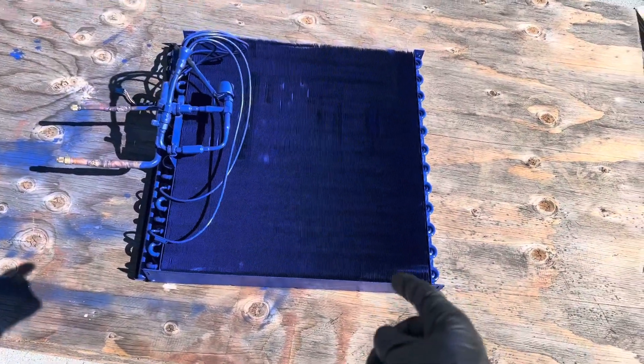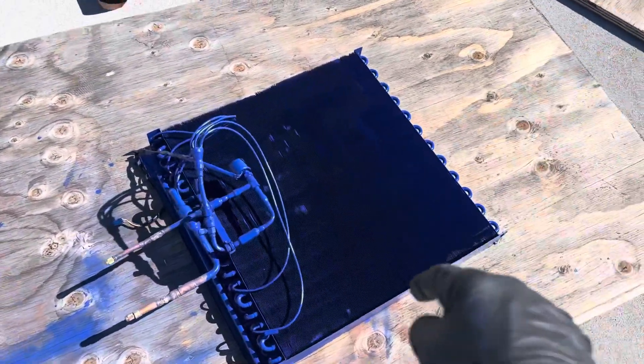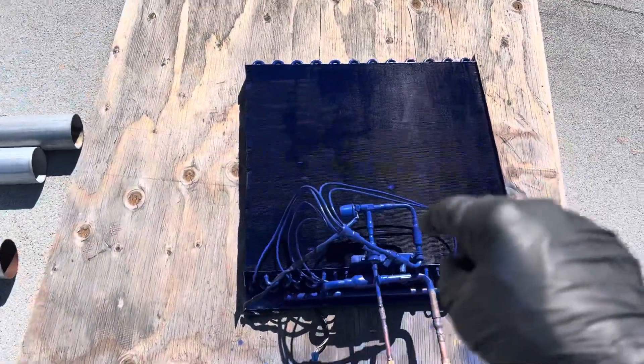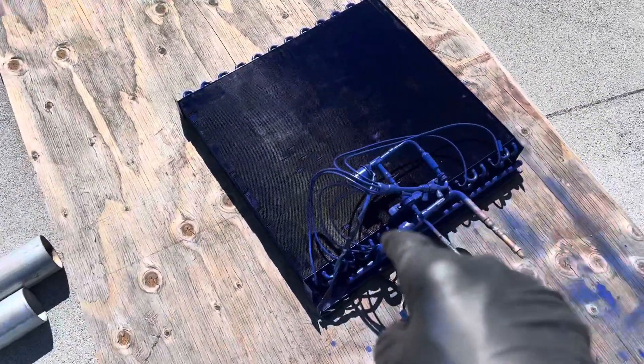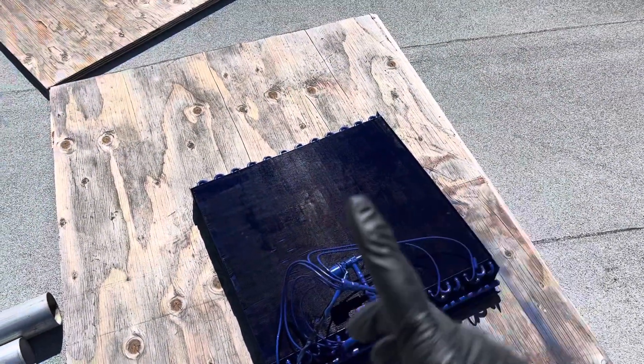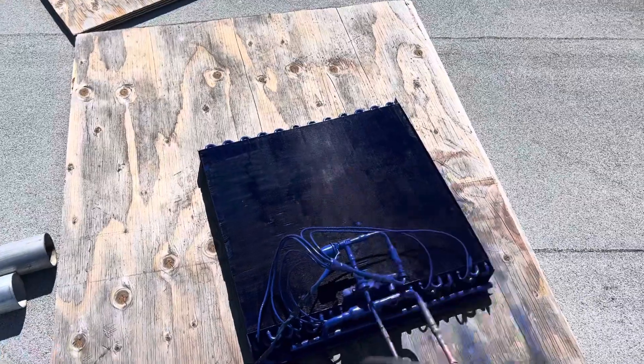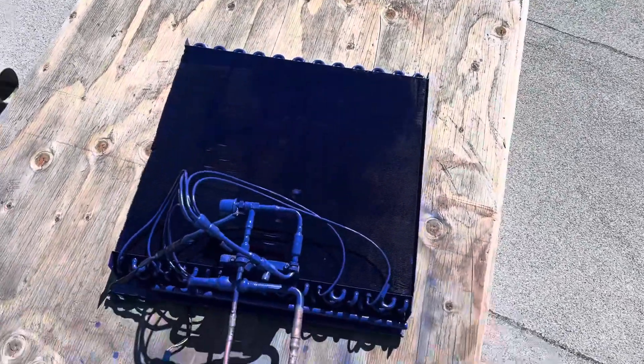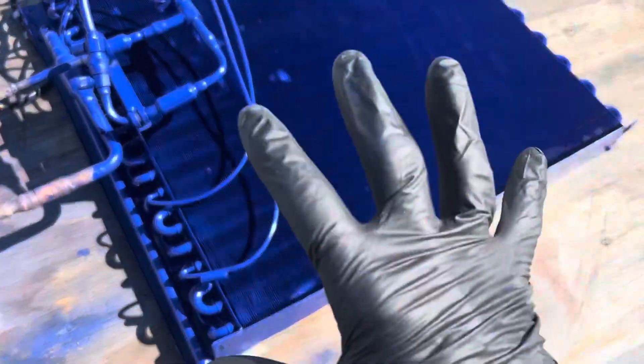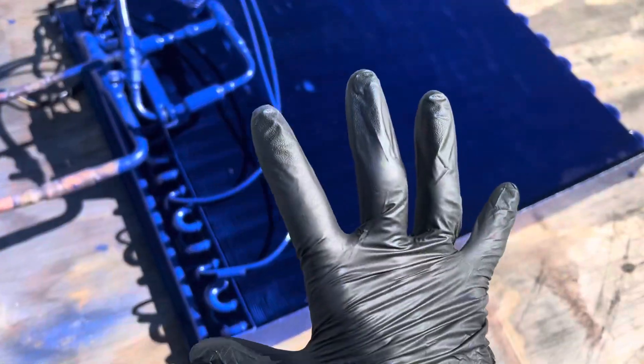This is the evaporator from a five-ton commercial Toshiba Carrier VRF unit that was leaking. There were five or six air handlers downstairs and this was the one. We finished repairing it and also gave it an epoxy coating — two coats.